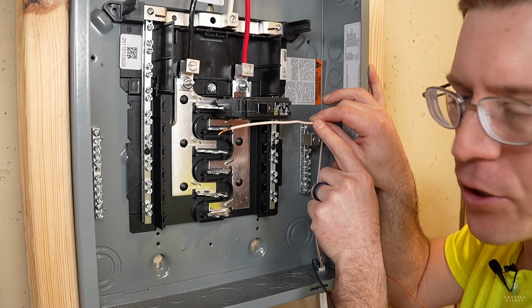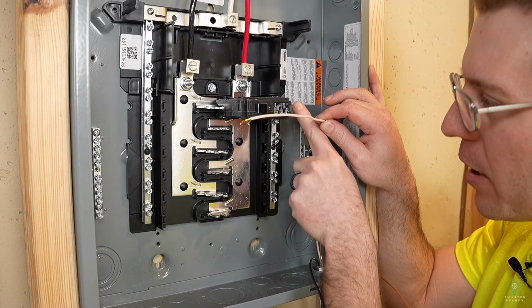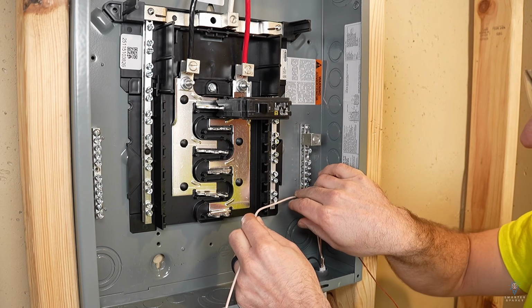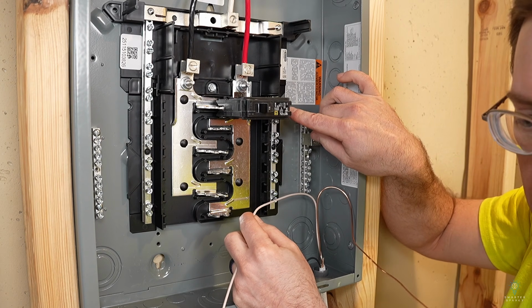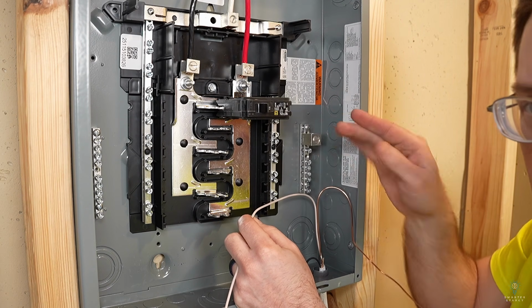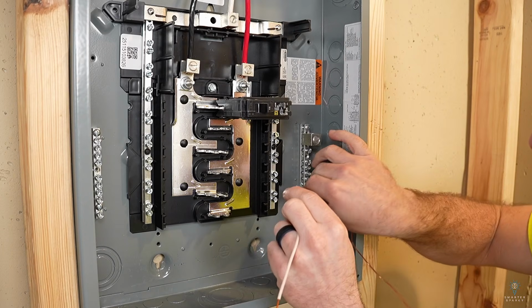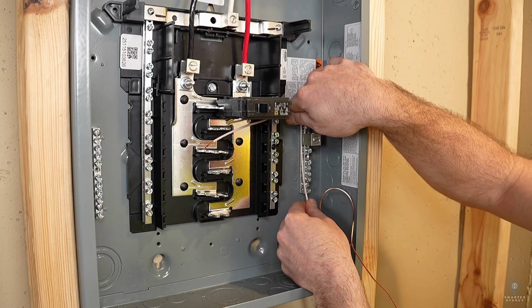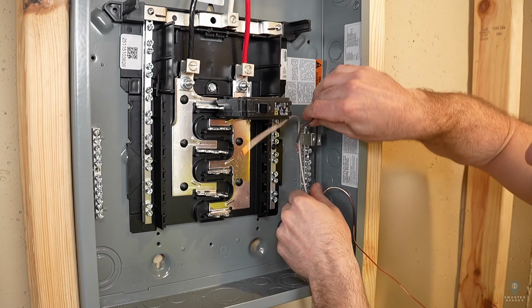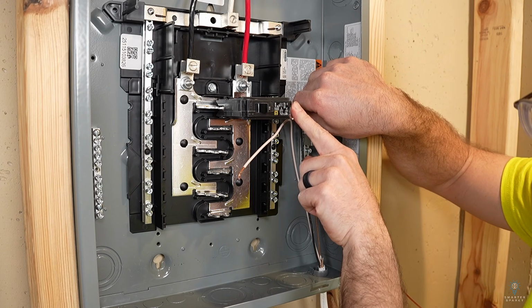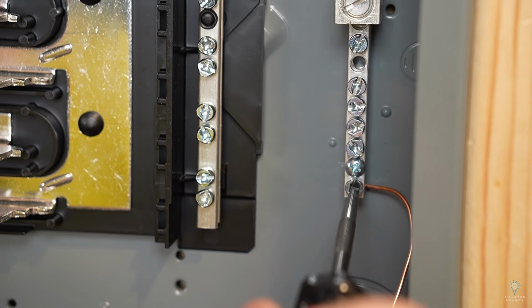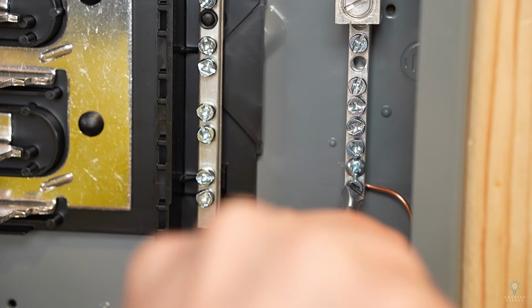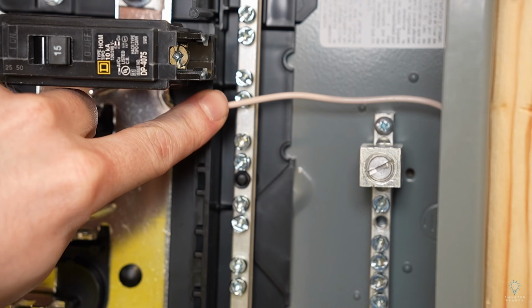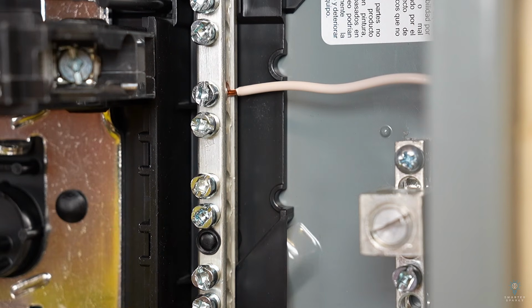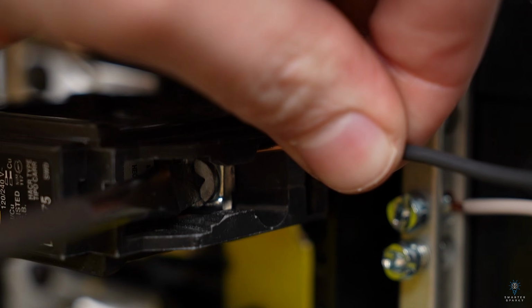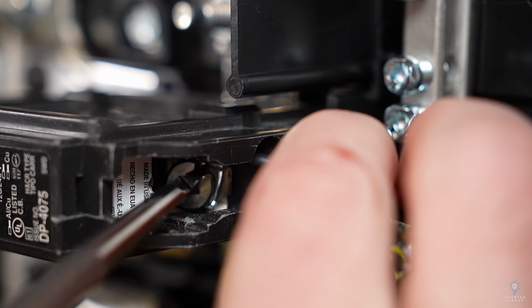It's good practice to land your neutrals near your circuit breaker if you can. There would be nothing wrong with installing this neutral down here, but if our circuit breaker is way up here, it might get confusing what neutral belongs with that circuit breaker. If we bring this neutral up here, we're going to land it right here, and our hot is going to land on the circuit breaker. So let's get this landed. I'm going to start with the ground wire, and then our neutral, looks like right about there. And finally the hot lands directly on our breaker.